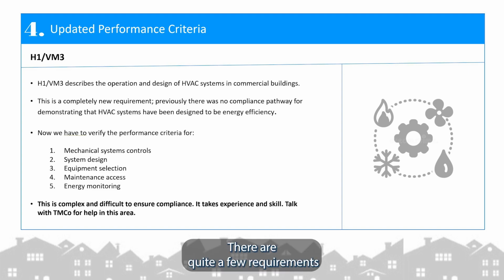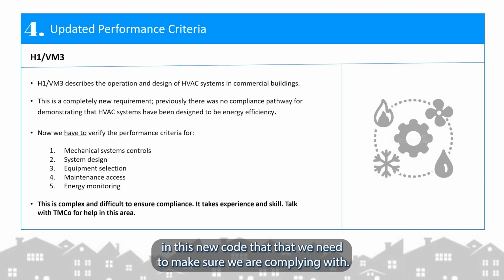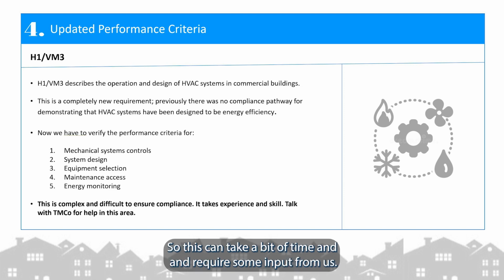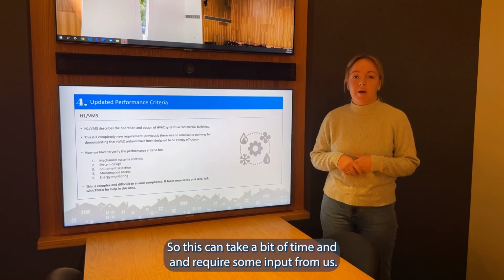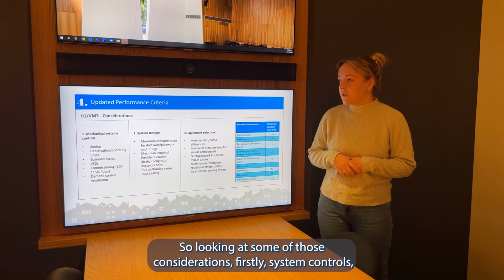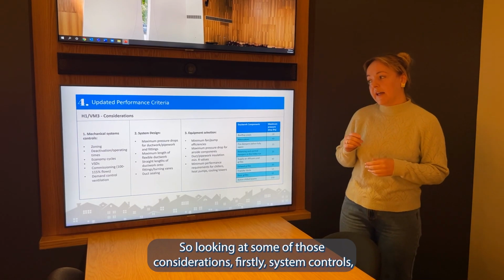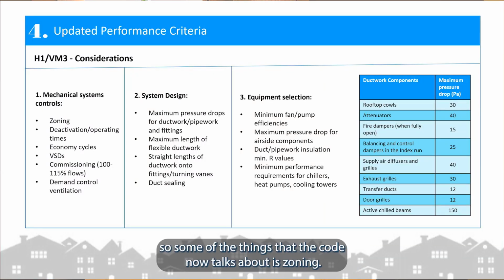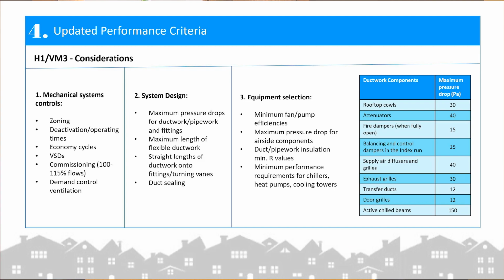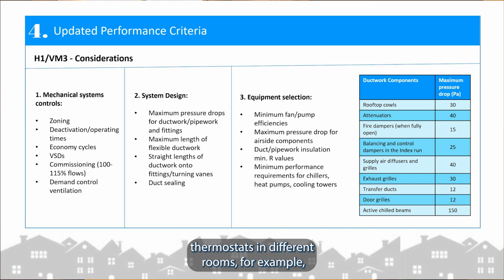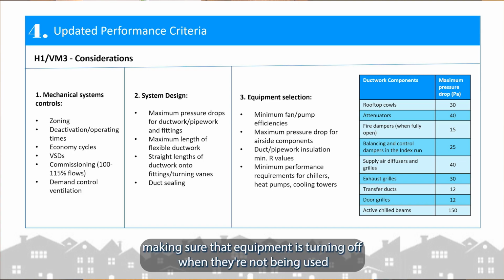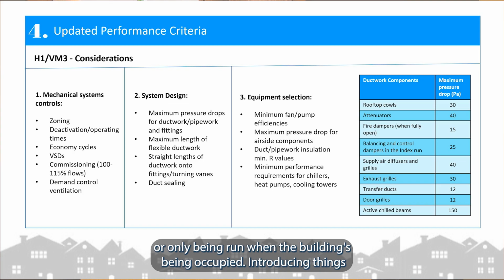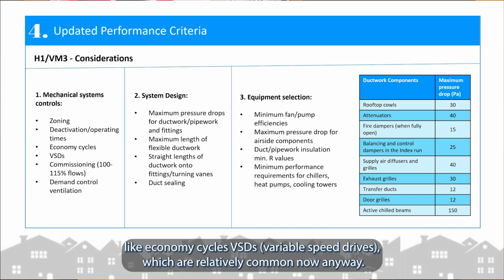There's quite a few requirements in this new code that we need to make sure we are complying with, so this can take a bit of time and require some input from us. So looking at some of those considerations, firstly, system controls. Some of the things that the code now talks about is zoning, so making sure that we have different thermostats in different rooms, for example. Making sure that equipment's turning off when they're not being used or only being run when the buildings are being occupied. Introducing things like economy cycles, VFDs, which are relatively common now anyway.